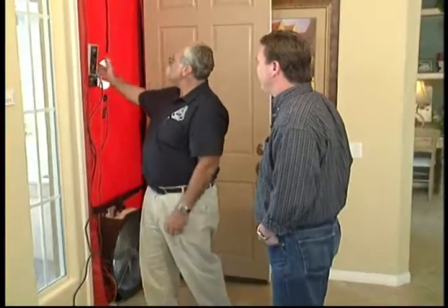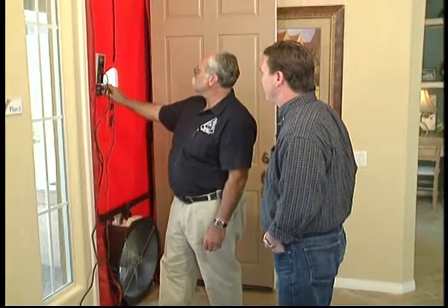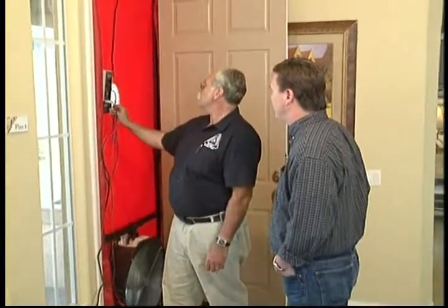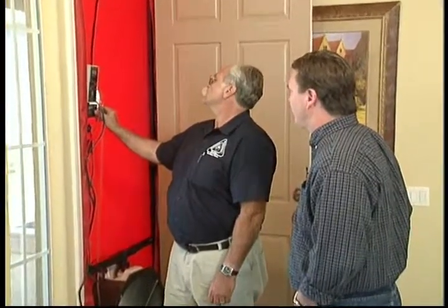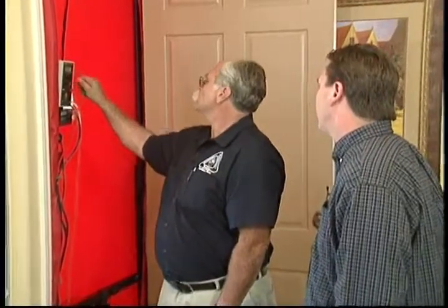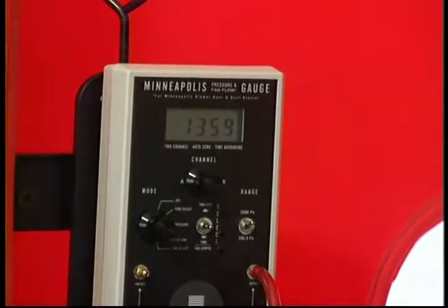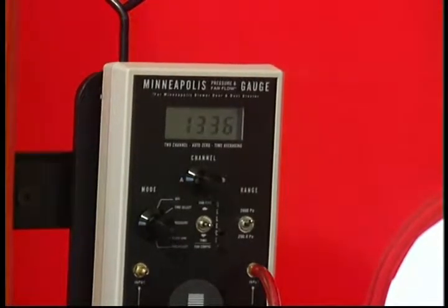And we can test this house, right? Oh, yeah. In fact, let's do that. I'm going to turn on the fans. Here's that membrane I was talking about. This is a manometer. This is a speed control that we can turn to set the RPMs of the fan. We just bring the fan up to a given pressure. As you can see, Steve, we came in at 1,347 cubic feet per minute at 50 pascals.